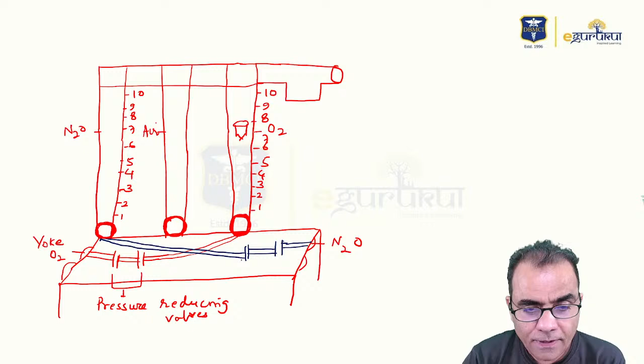So when gas passes all around this bobbin, due to these cuts, it will make the bobbin rotate. If your bobbin is rotating, that indicates that your gas flow is continuous. One thing. Second, it is the upper level of the bobbin which determines the flow rate, not the mid level or lower level, upper level.